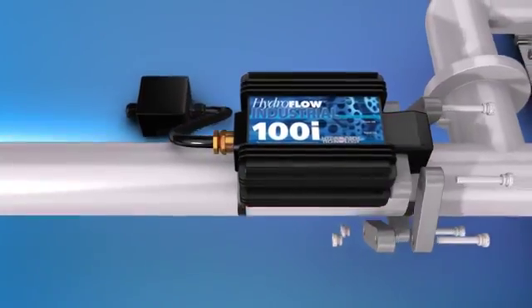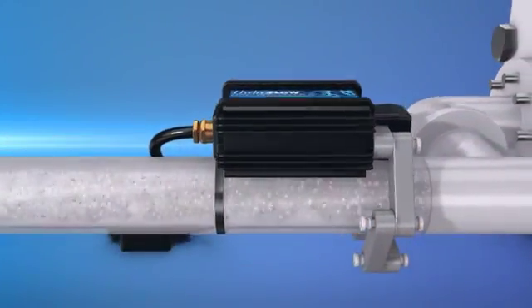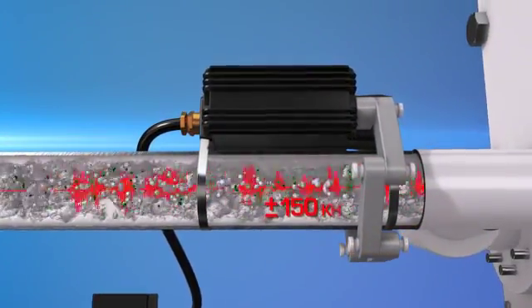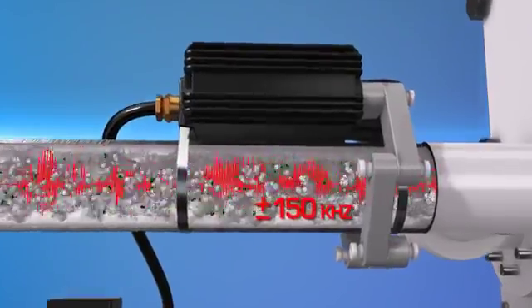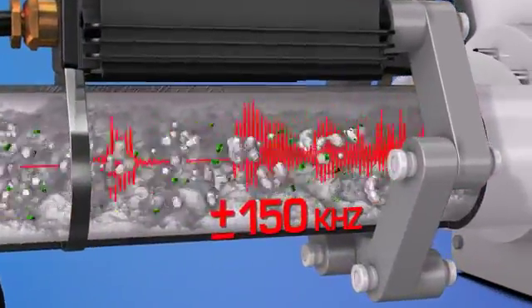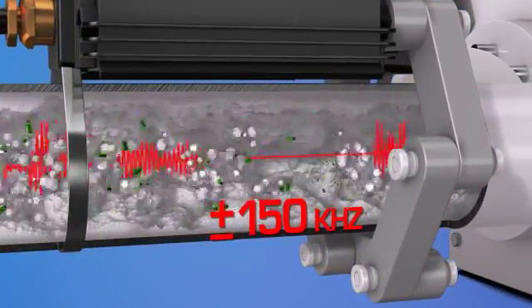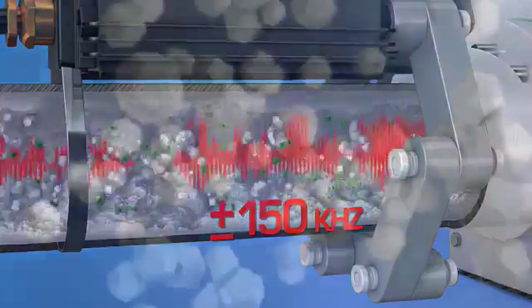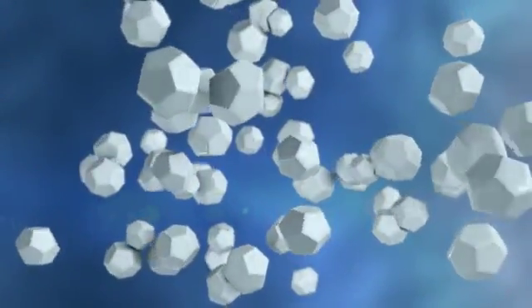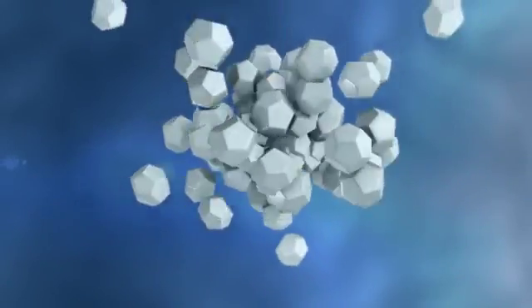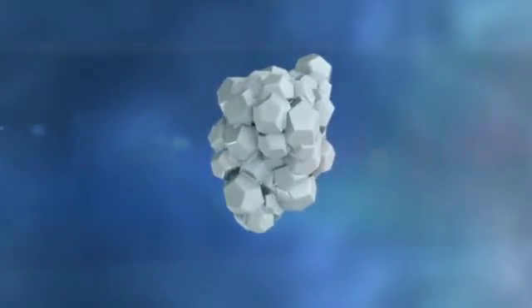The Hydroflow water conditioner applies an electric signal of 150 kHz throughout the piping system, causing the ions to form clusters. When supersaturation occurs, the clusters precipitate out of the solution and form stable crystals which do not adhere to piping and equipment.